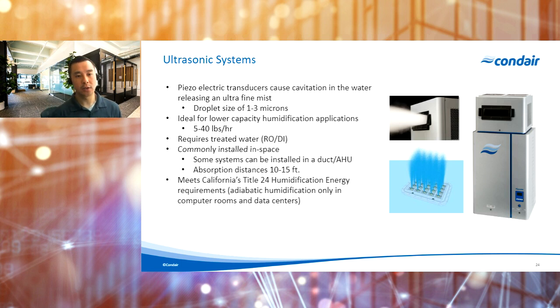So the last technology that we will look at here is what we call ultrasonic or nebulizer type systems. The way that these systems work is we have a series of piezoelectric transducers submerged inside of a sump. Those transducers oscillate at an ultrasonic frequency, which causes cavitation in the water, and that releases an ultrafine mist into the airstream. So very similar to high pressure atomizing systems, with ultrasonic systems, we do need treated water as well. So either reverse osmosis or deionized. And again, the main reason here is to prevent any of those minerals from precipitating out as a dust as that mist evaporates, and also to prevent clogging or scaling of the transducers.